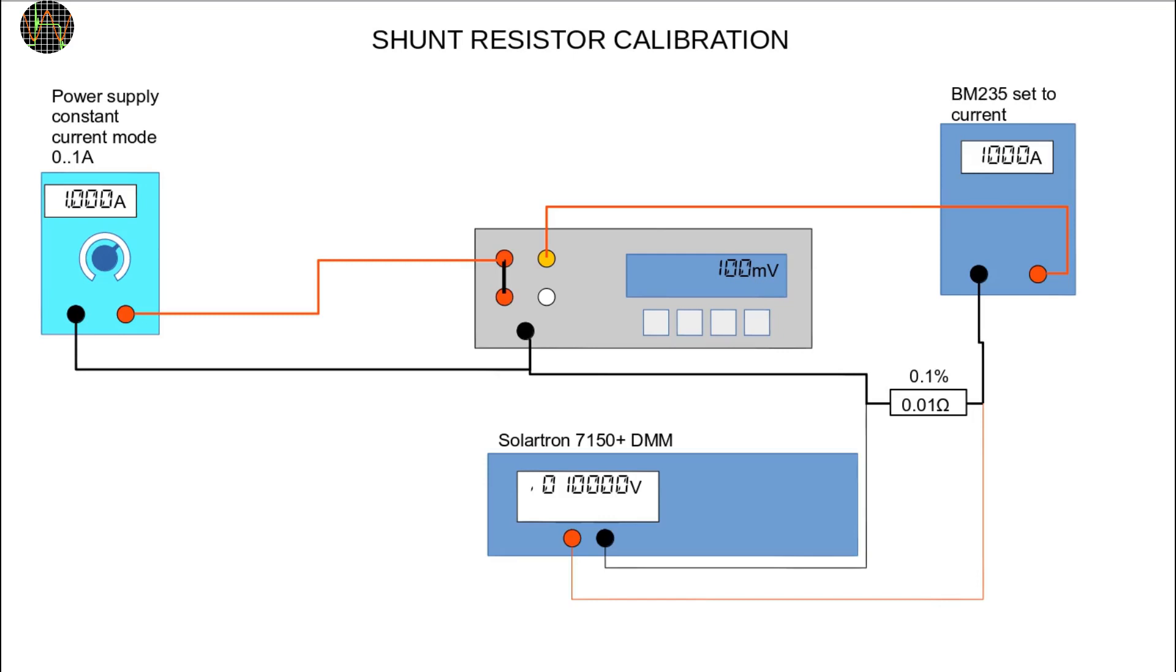The setup for calibrating a shunt resistor. For this you need a power supply that can generate 1A. The current is measured by the BM235 and by the Solartron 7150+.